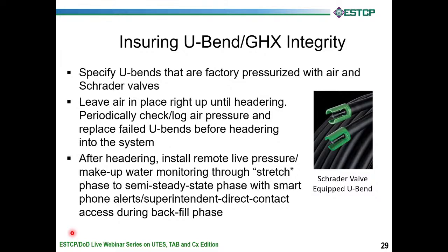And if you're also monitoring, as Brandon mentioned with the hydrostatic pump there, how much flow you're letting in, then you know whether you're net continuing to add water. And after a certain period of time, you should not have to add any water in there. But HDPE piping does stretch. And so you've got to take that into account, that you will need to put water on it for a while.